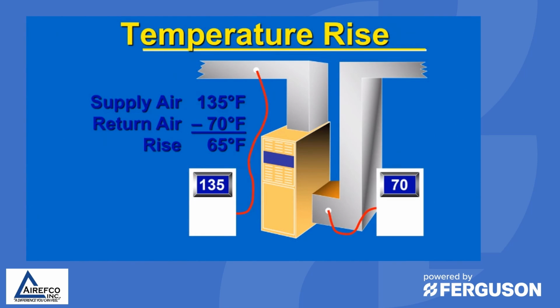Another check that we usually make on a gas furnace is the temperature rise. On all gas furnaces, there is a range of temperature rise that is listed on the data tag of the furnace. By taking the return air temperature and the supply air temperature down the ductwork away from the radiation heat of the heat exchanger, we can subtract these two and get our temperature rise. This will tell us if we are in the range that this furnace is designed to operate in. Also note that just because we have the proper temperature rise doesn't mean that there may not be some turbulence in the supply or the return ductwork that is causing the furnace to trip on a limit switch. So make sure you check out the ductwork and how the air is flowing through the furnace, and make sure that you don't have any turbulence that is causing issues.